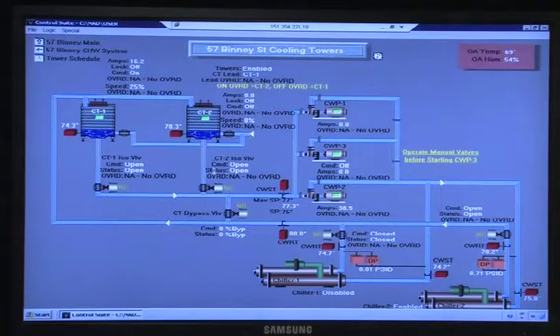So I'm going to head down here and say this is tempered, cooled down, returning water coming through here. It picks up a sensor, and that's what it's trying to maintain here. And for the sake of argument, not to interrupt you, the cooling towers originally, with one tower enabled, one tower went with one pump, the other pump went with the other one. The isolation valves associated with the tower would open if that one was enabled to run, the other one would remain closed.